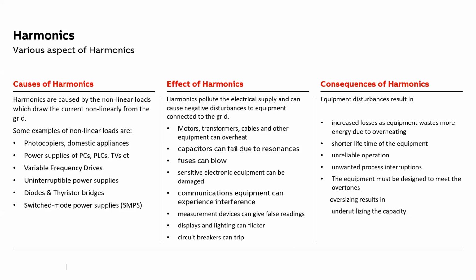So now, what is the problem with harmonics? Basically, harmonics cause overheating. One more thing we need to understand about harmonics is that harmonics travel backwards. They travel from the generating device towards the power source. For example, if the VFD is generating the harmonics, they will travel backwards to the main feeder, and from there to the main transformer, and then to the grid also. That is the reason the power supply companies and the regulatory authorities are now becoming very strict with respect to harmonics and the power factor. So one, it travels backwards, and then it affects your motor, the transformer, the cables, the intermediate equipment, everything. It causes overheating in these equipments.